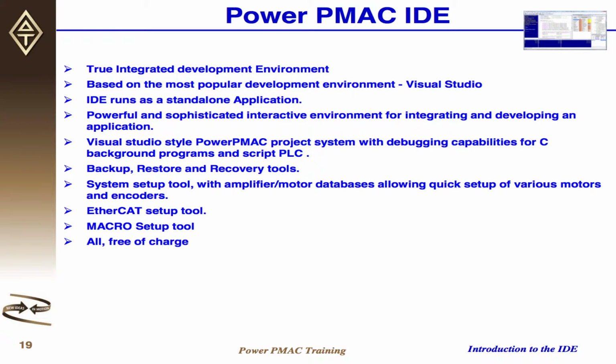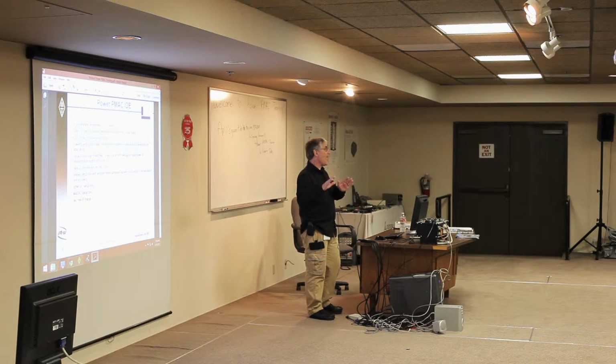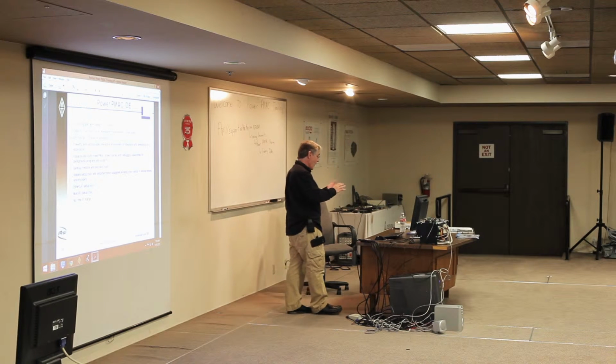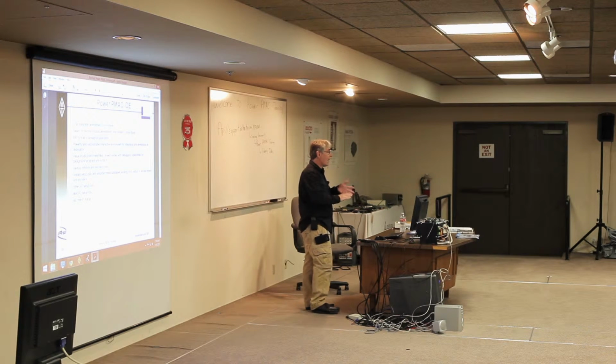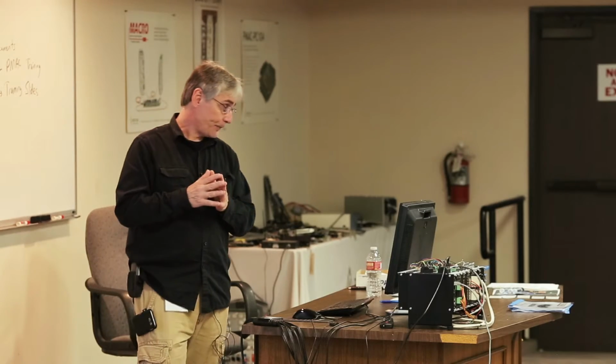There are tools for backup, restore, and recovery. There is a system setup tool. One of the nice features about the system setup tool is you don't really have to understand a lot about what's going on behind the scenes in Power PMAC. You need to only know the parameters about your motor, about your drive, what your feedback devices are, what type of feedback devices they are, and then the system setup tool will automatically configure Power PMAC, what we call the structures, and I'll be talking about that very shortly. That is the mainstay of what makes Power PMAC Power PMAC.